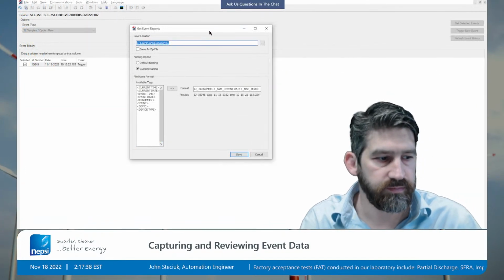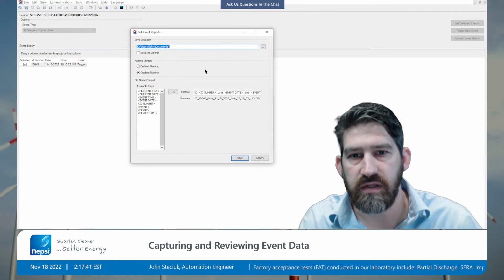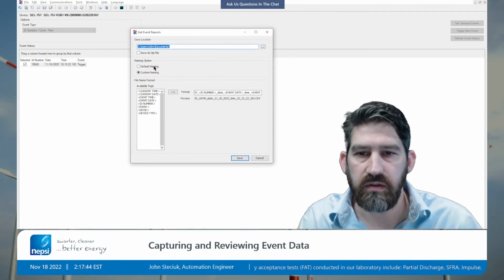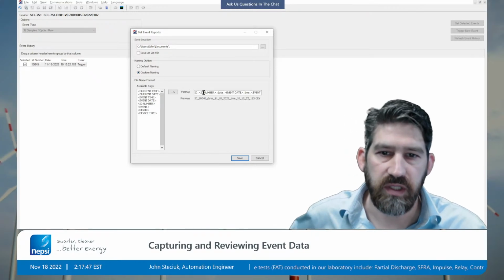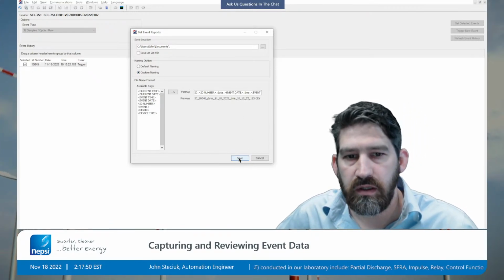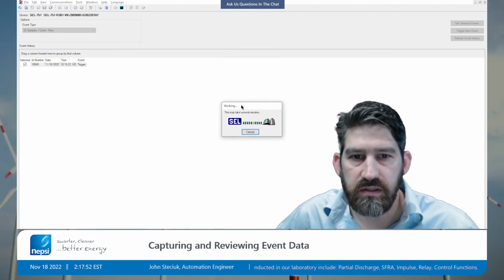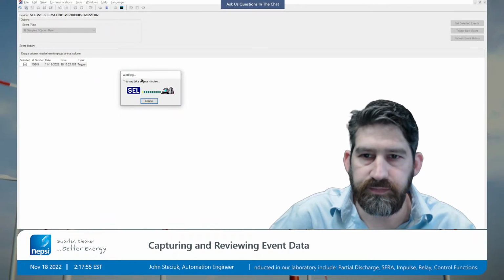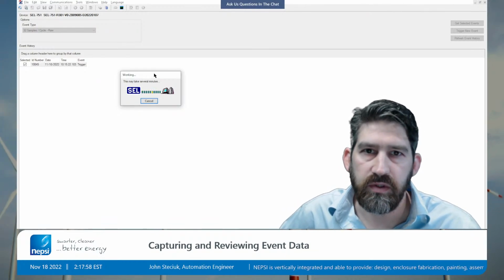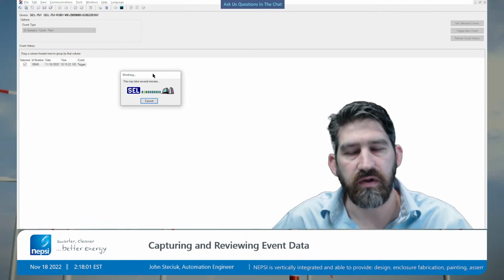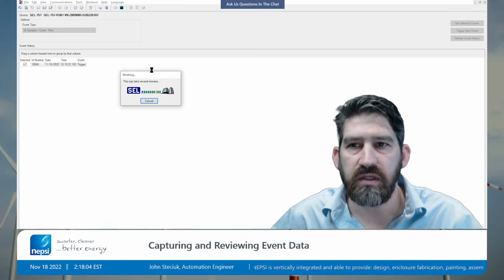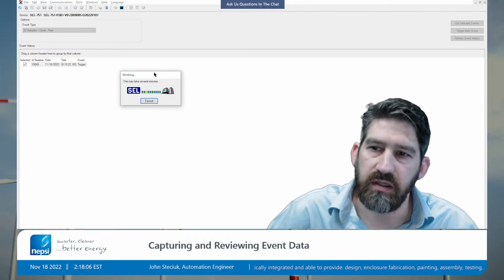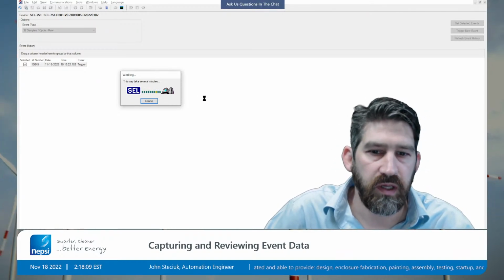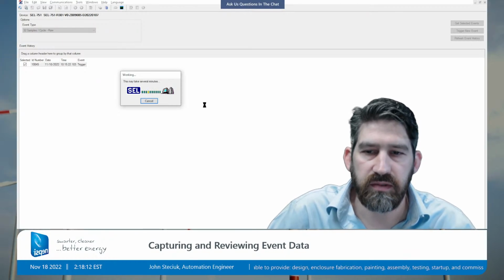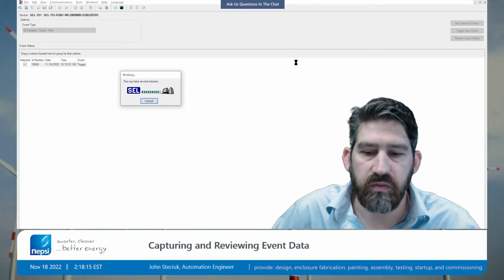Brings you up to a page where you can name the file, choose the save location. You can use default naming or custom naming and change it all right here. Then you click Save, and it takes a minute to get the event report. It takes quite a bit longer if you're using the SEL serial cable. So I recommend if you're doing this, try and use an Ethernet cable. It'll save you a little bit of time, especially if you're getting multiple event reports. I mean, it could take up to a half hour to get 10 of these downloaded with a serial cable.